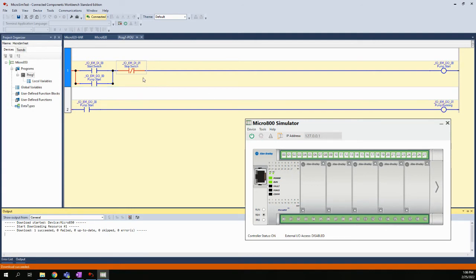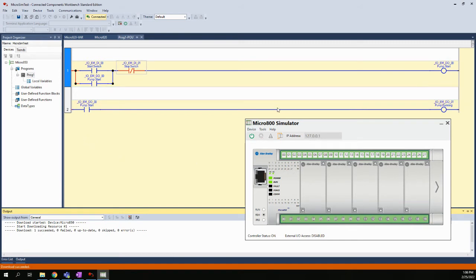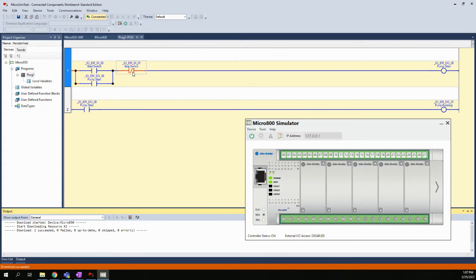I am connected online and connected to the simulator. This would be the same exact look and feel if you are connected to the real controller. The background turns yellow—that's a default color which you can change. My contact here is showing as red and some are showing as blue. When it's showing as red, it basically means that it is what we will term passing power, even though it's digital and there's no power, so to speak.